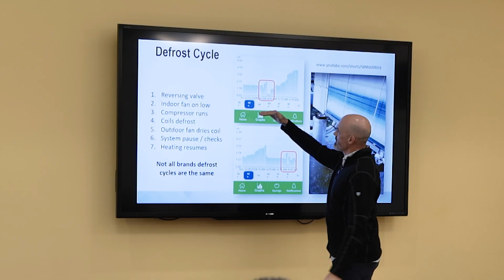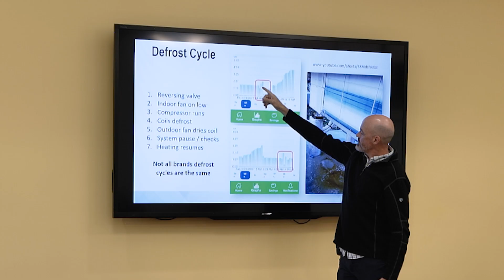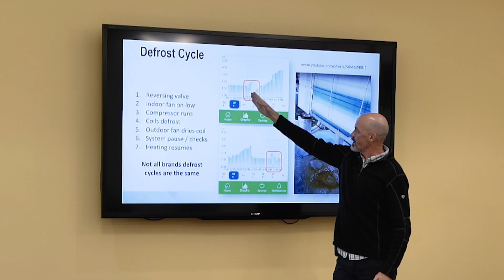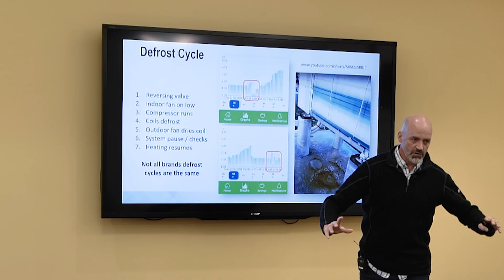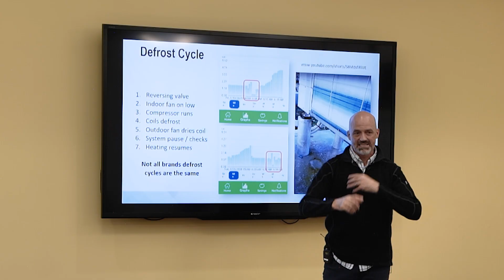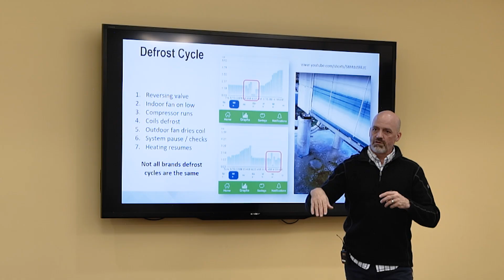So real quick, using that energy monitor, I'm trying to highlight what the defrost cycle looks like. We've got this point where it stops — that's the first column there. Then you'll hear the compressor: the system stops running, the reversing valve switches, and the compressor ramps up and defrosts itself. It generates heat internally to defrost itself and runs it through the coil. It does steal a little heat from the house, but the indoor unit coils are off as well, since it's a refrigerant loop.